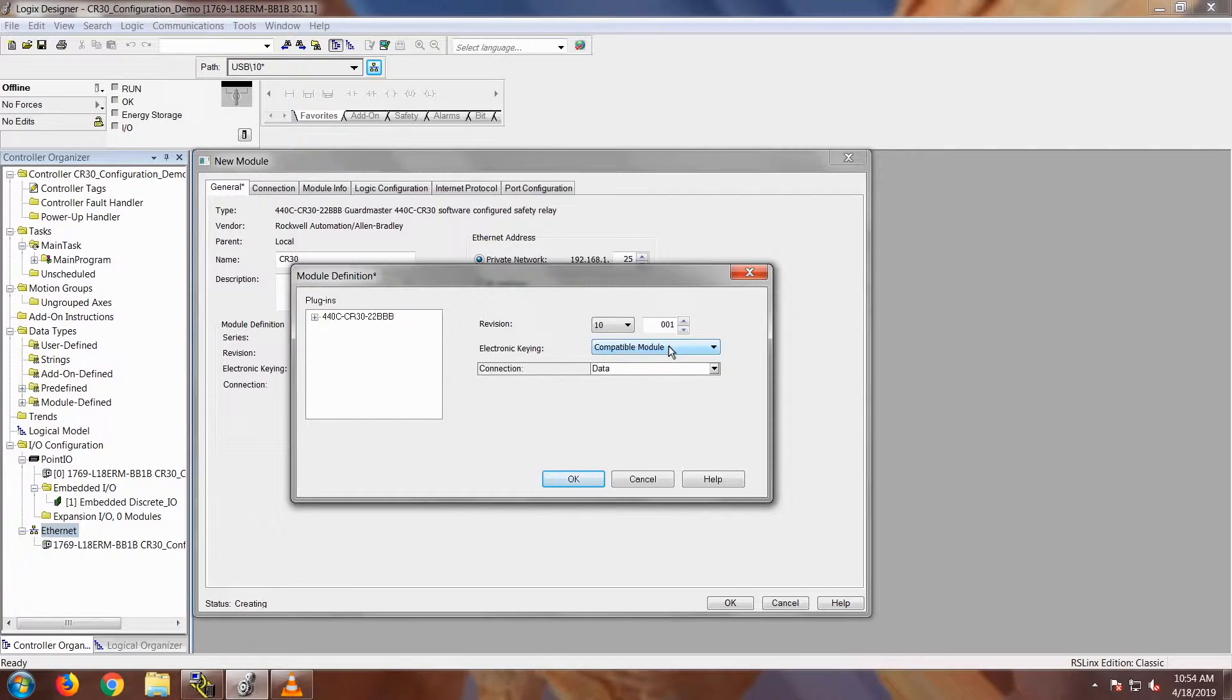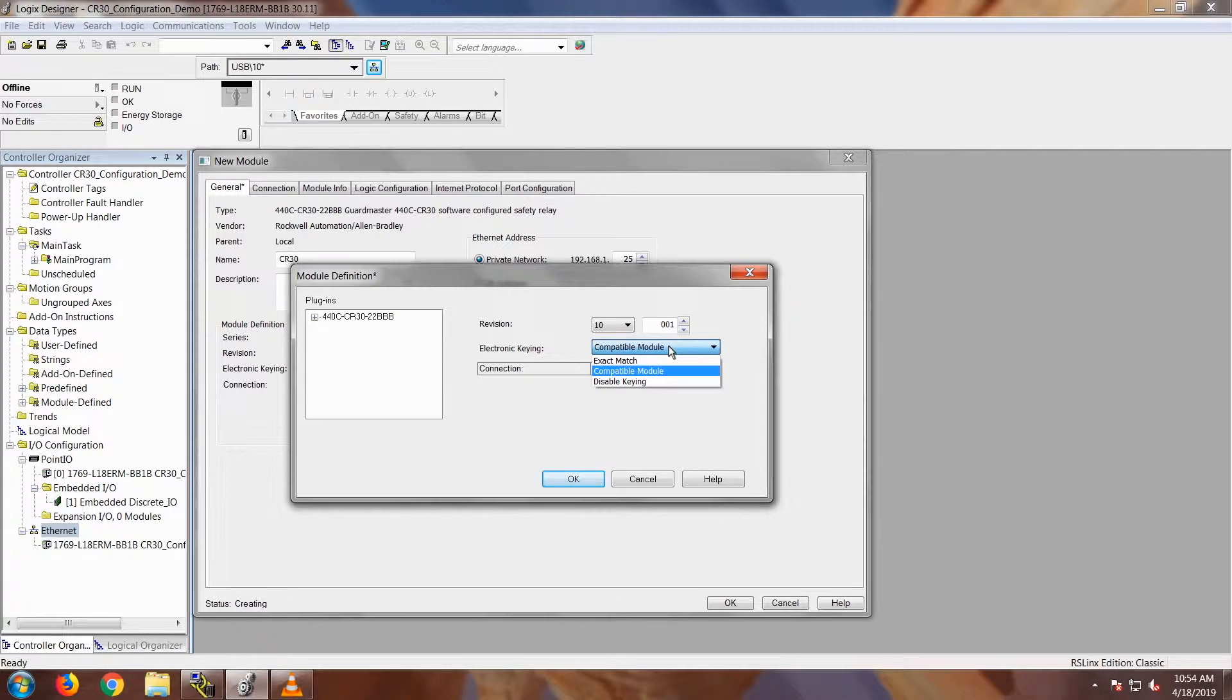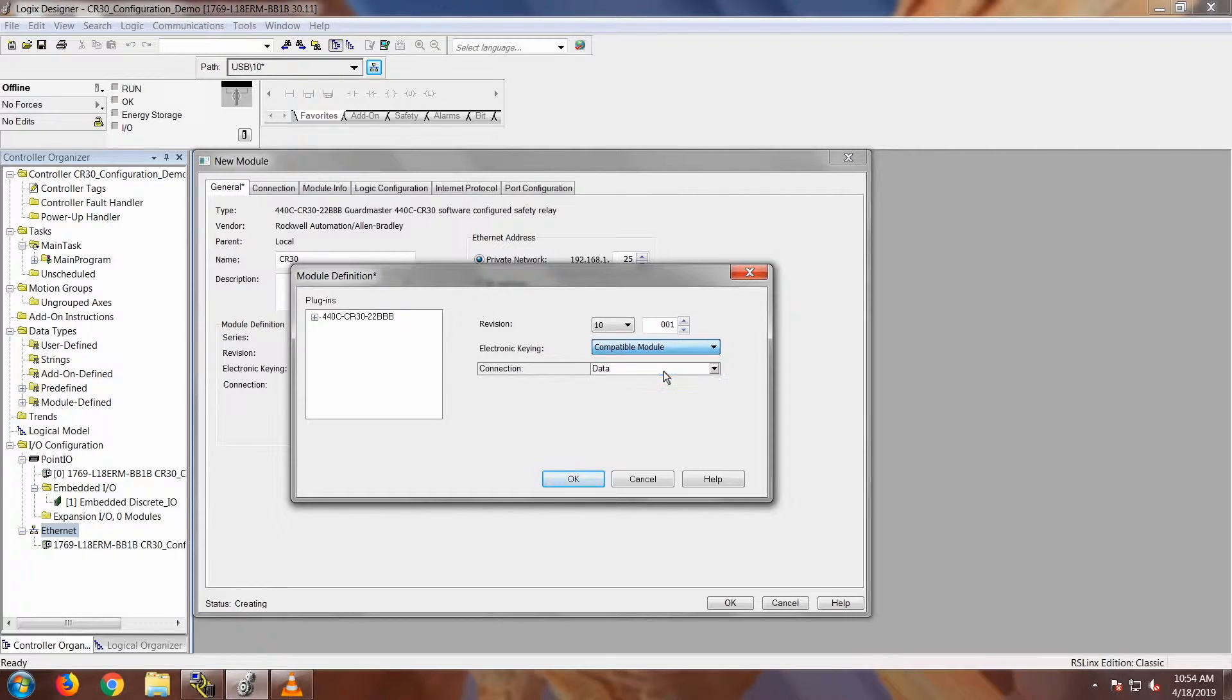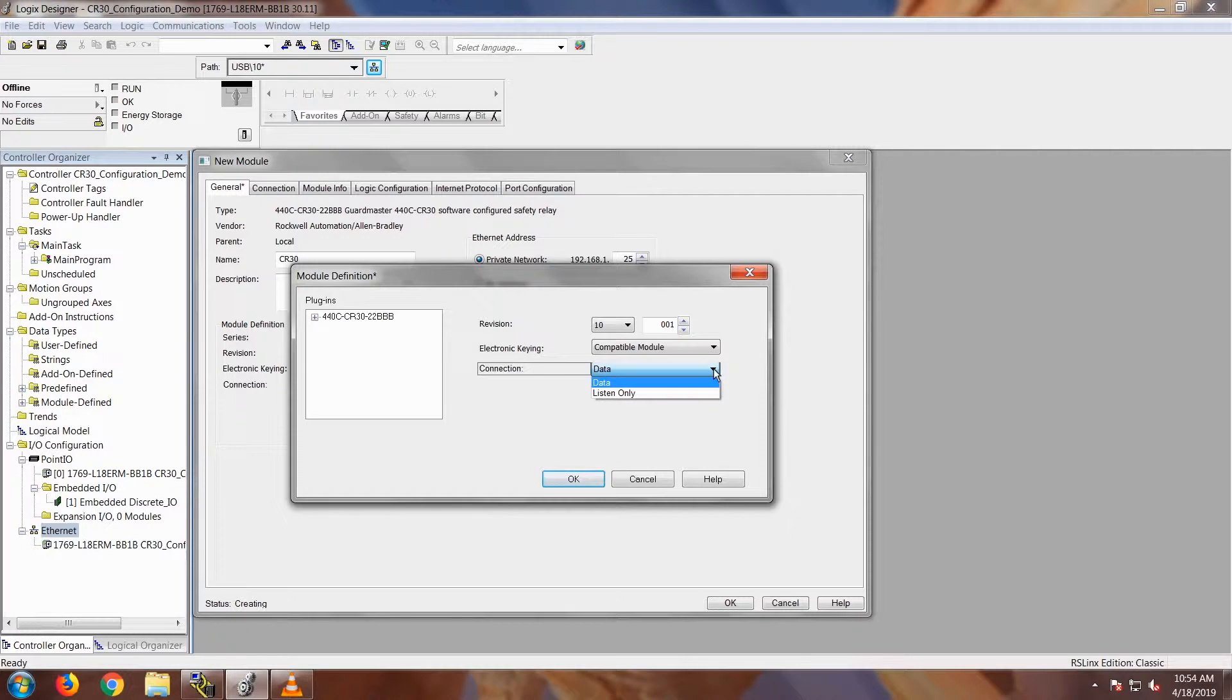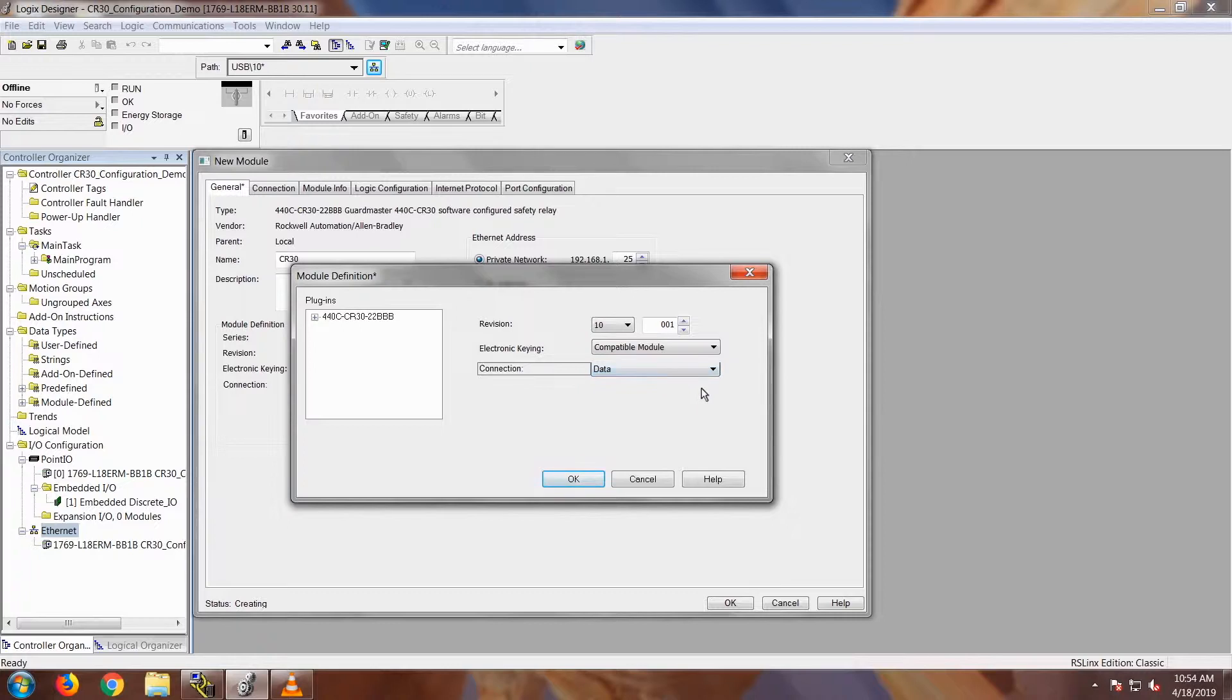Electronic keying, I'm going to keep it at compatible module. This is where you can put exact match, compatible module, or disable keying. We'll keep it at compatible module. It doesn't care about the small revision number, only the large revision. And then our connection point we're going to keep at data because we want to actually communicate and work with the CR30 instead of just listening.